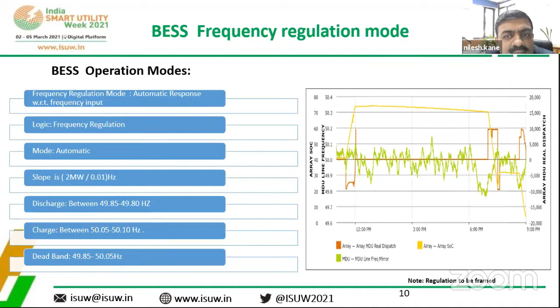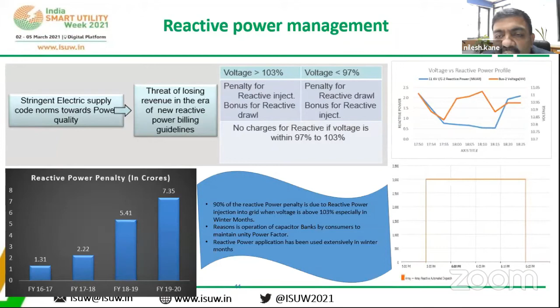Reactive power management: capacitors are used to take care of the under-voltage problem, but for over-voltage, generally all utilities end up paying a huge penalty. In our case, we paid around 8 crores of rupees because we had no solution, so the battery plays a very important role. From 97% to 103% we generally operate the grid, but whenever voltage exceeds 103%, especially during winter seasons or when bigger consumers operate capacitors continuously, the battery has played a very important role. These pictures show how we used it to take care of the voltage profile for our utility.